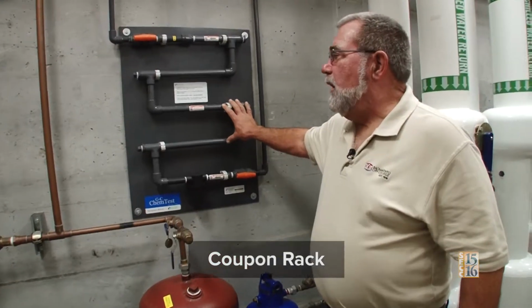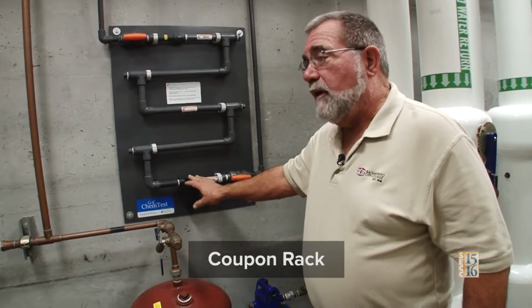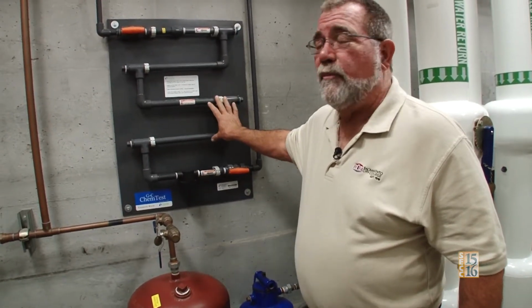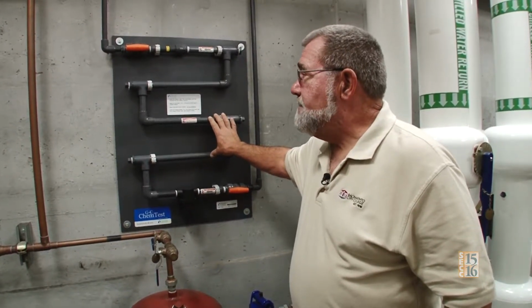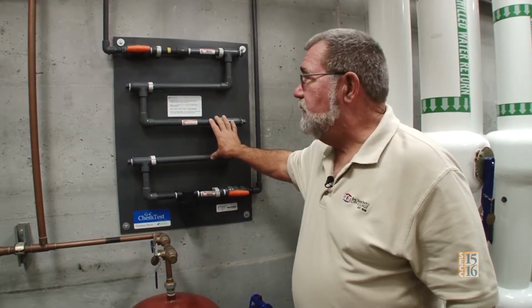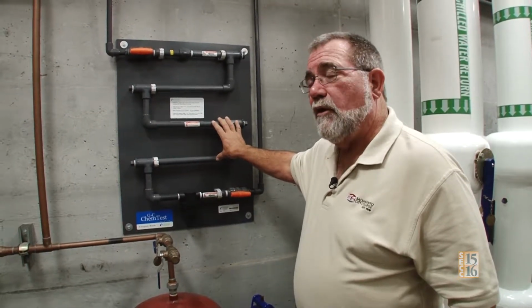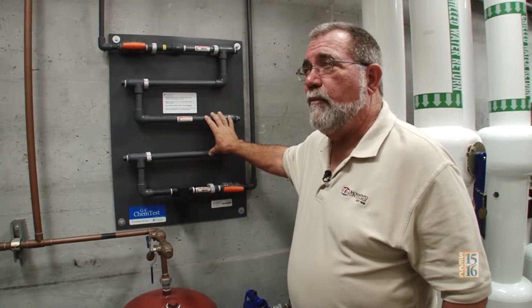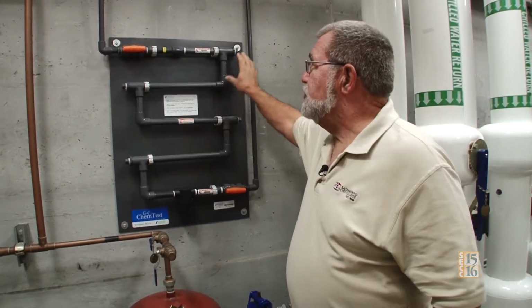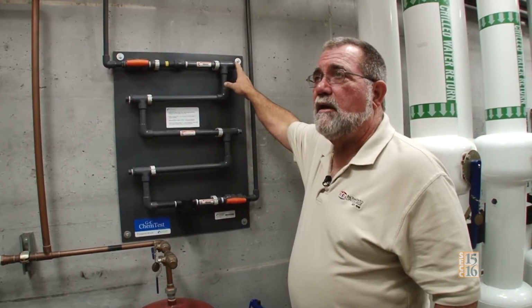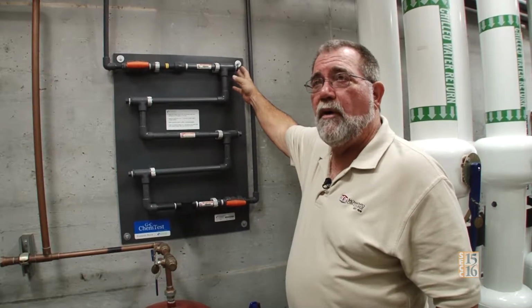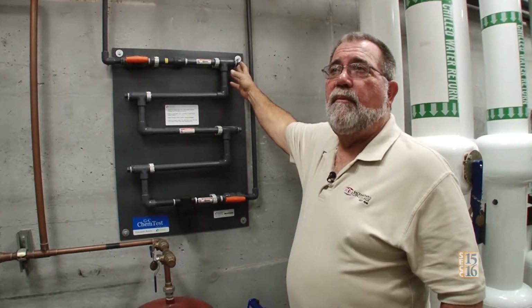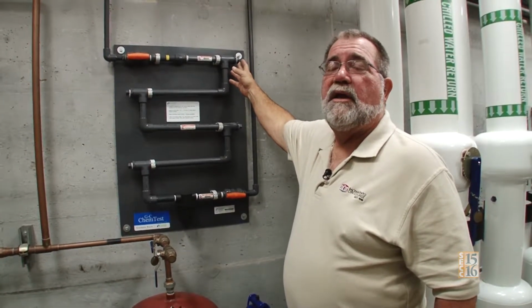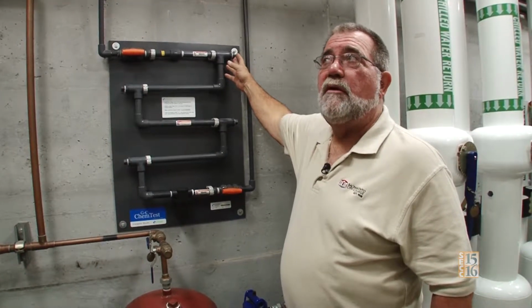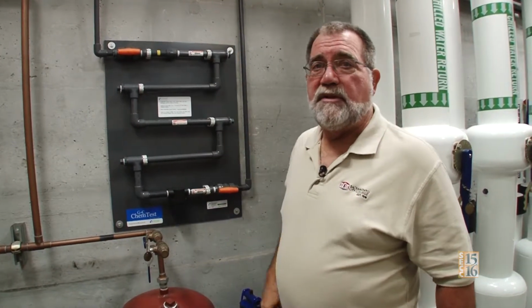This is a coupon rack supplied by Garrett Callahan, who also support the program, especially with water treatment chemicals for our chill water loop, hot water loop, and steam boiler. Here the students can see how we put in coupons and then pull them out to measure the corrosion rate occurring within our piping systems.